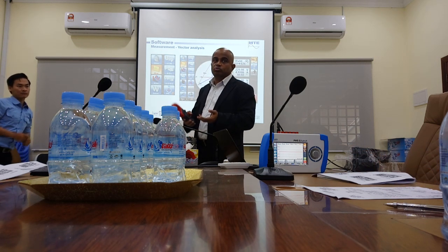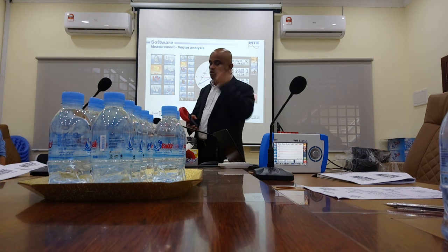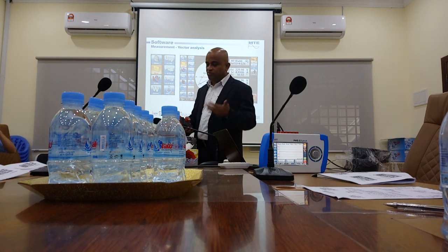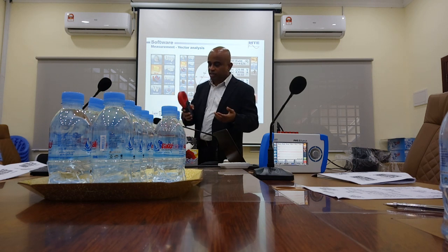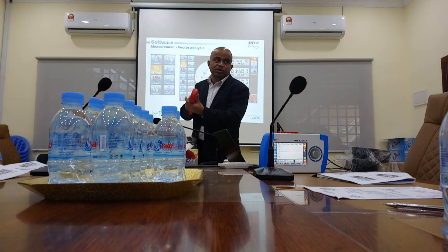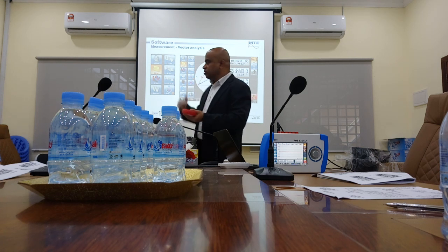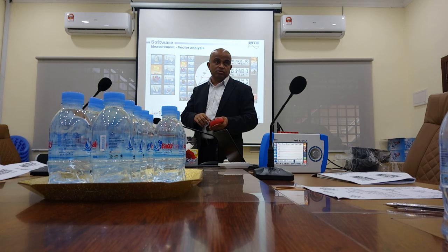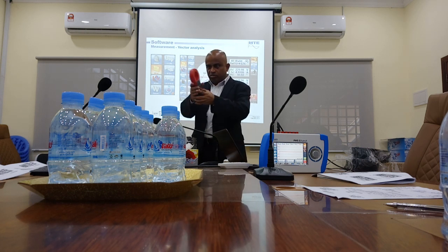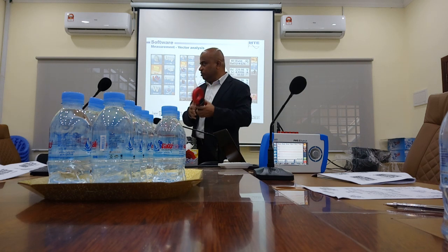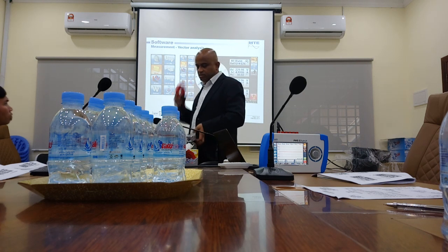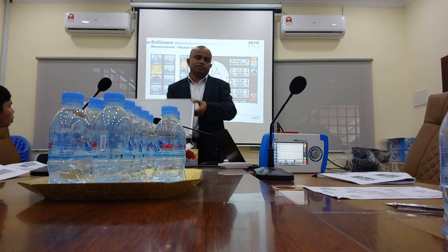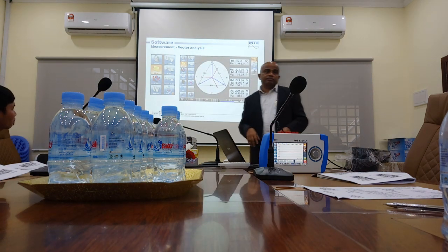Sometimes you also make measurements there, and you think you are very careful. Even sometimes we experts also make mistakes. You go to the site, you climb like this, then you reverse it unknowingly, and then how to know? You just look at the waveform, you look at the diagram, you can straight away know what is wrong. Easy. Sometimes you think it is positioned right, but the wire may be coming the other way around. Yeah, so you can spot mistakes very fast by using the vector diagram.